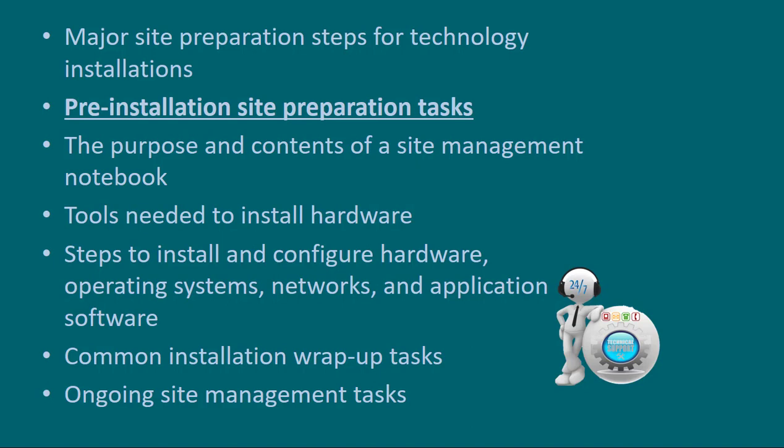A dedicated circuit for hardware devices is preferable, especially in a server room. Especially for such things as a larger UPS, uninterruptible power supply, you want to have a dedicated circuit for this, not a shared circuit. It's okay to have a shared circuit for desks and certain areas, but when it comes to our servers, which are going to be plugged into more than one UPS so that you have that failover ability, make sure those are dedicated circuits and know where those are at in your circuit breakers, so that if something goes wrong, that is going to limit your troubleshooting.